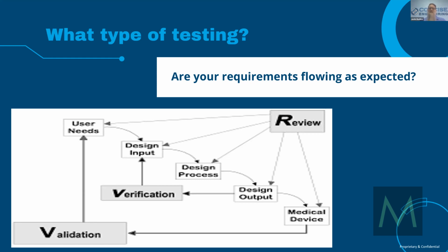And here you have the design outputs have to meet the design inputs. That's your verification realm. Generally, you can think of this as anything that you're doing inside, in your lab, in your company. And then the validation side is where you're actually interacting with the users. You're looking at your KOLs, your doctors. They're handling your finished product. They're telling you that the labeling and the IFU is good. They're telling you that they feel like this product is safe and effective. You can also lump in usability and some other things within this validation, but they are not the same. So you've got design validation for your product and usability validation for that aspect. And then you've got software validation, which really kind of falls into the verification bucket. There are a lot of nuances, but this is primarily what the FDA puts out there.